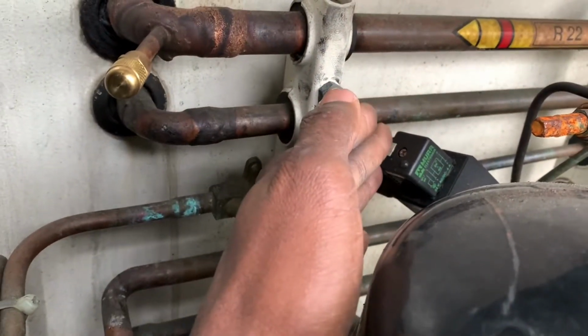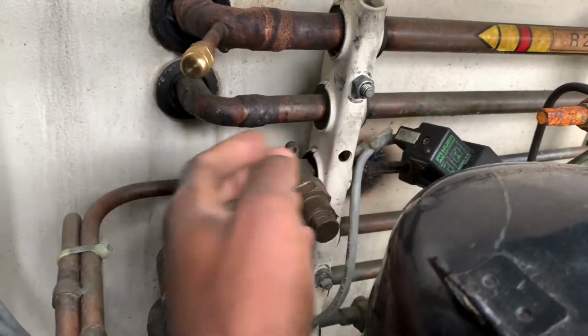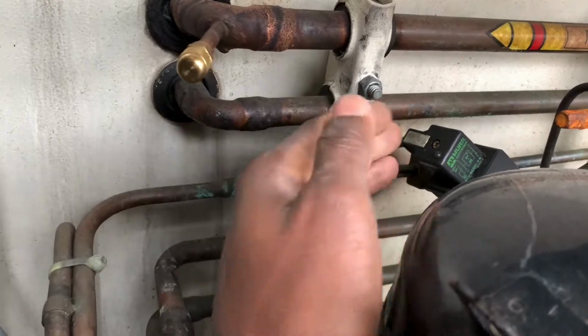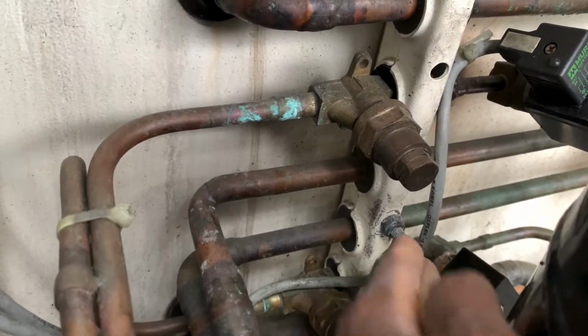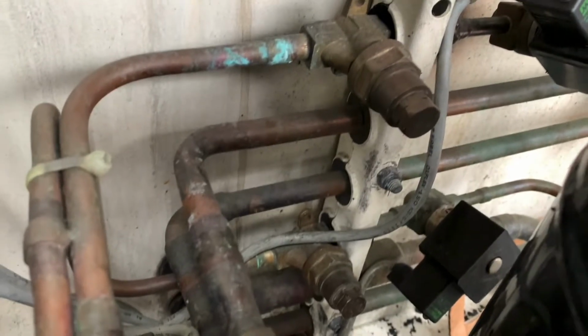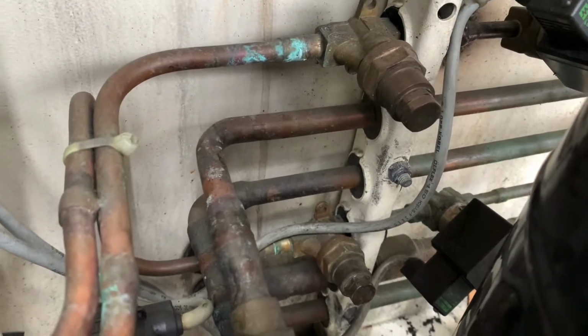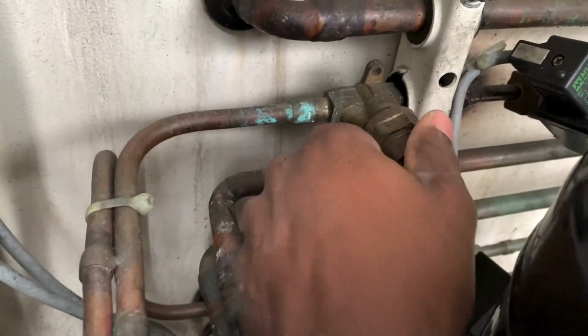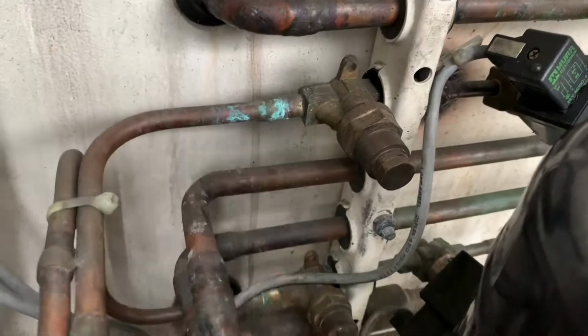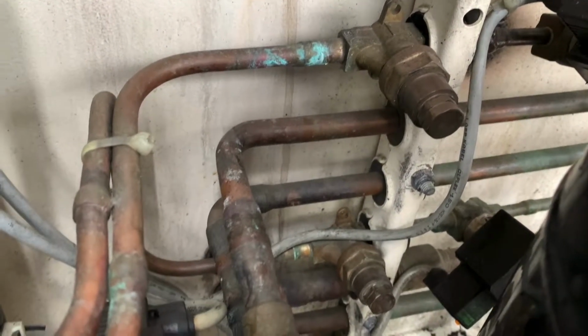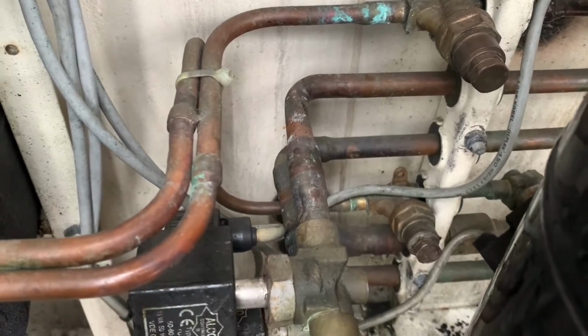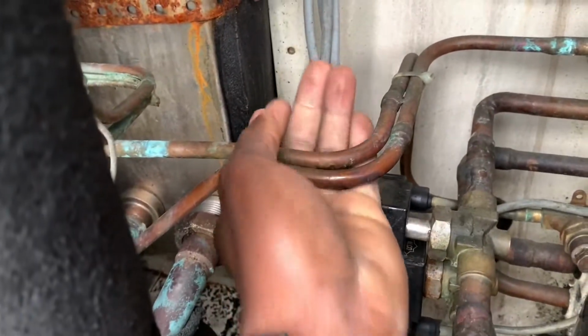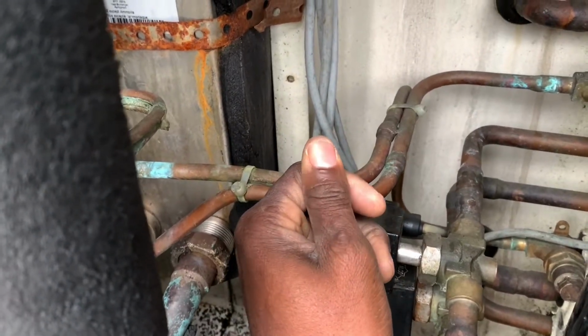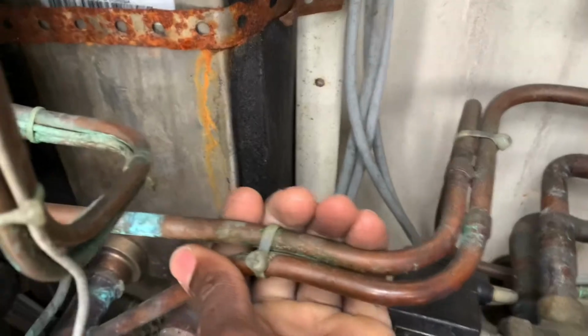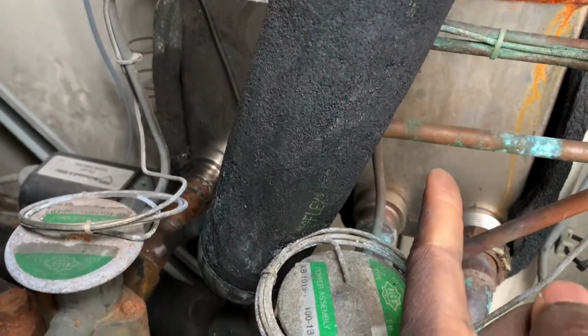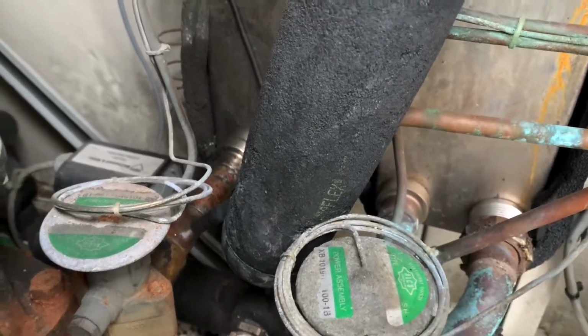This right here is the capacity control solenoid for circuit number 2. Alright, and then in the bottom there, that's your capacity solenoid or hot gas solenoid for circuit number 1. And you can also remove these caps and adjust the valve, how much gas you want to pass through. Okay, so this line right now is hot, the one for circuit number 1, because it's going right into the evaporator or TXV, evaporator inlet, TXV outlet.